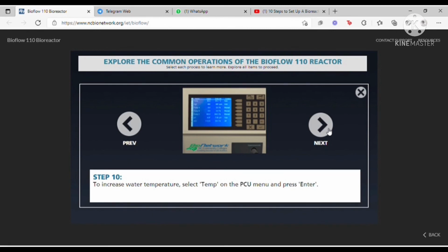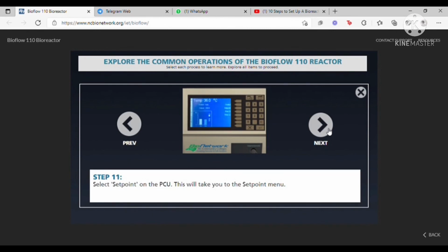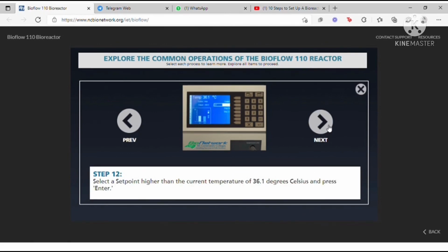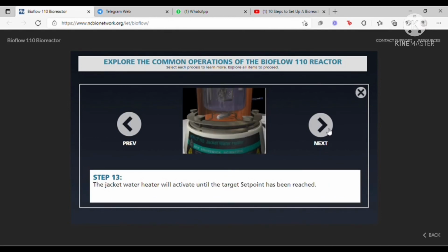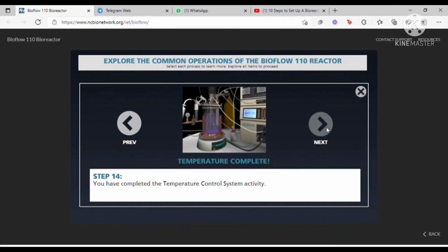To increase the water temperature, select temp on the PCU menu and then press enter. Select set point on the PCU, this will take us to the set point menu. We then have to select a set point higher than the current temperature of 36.1 degrees Celsius and then press enter. Step 13. The jacket water heater will activate until the target set point has been reached. Activity is complete.